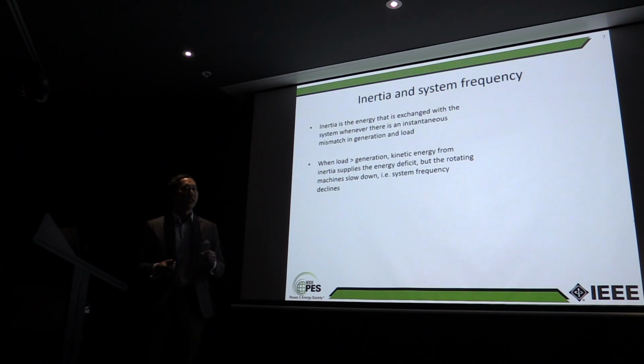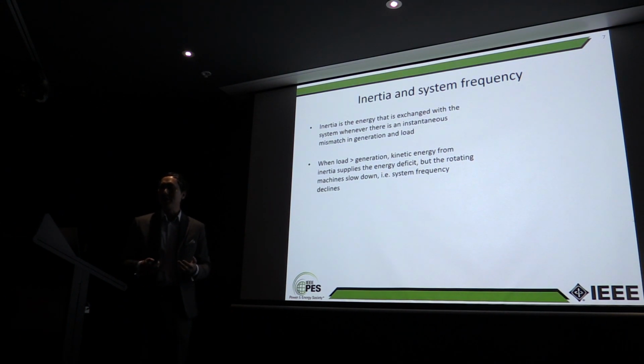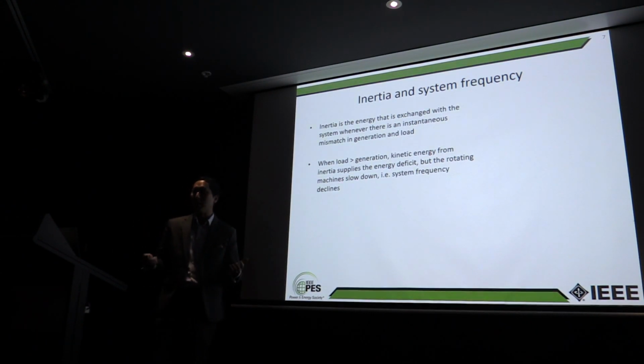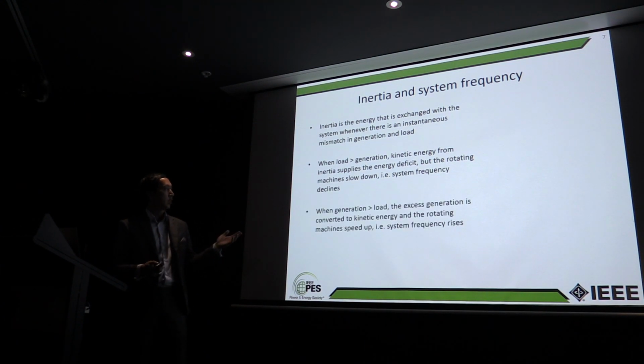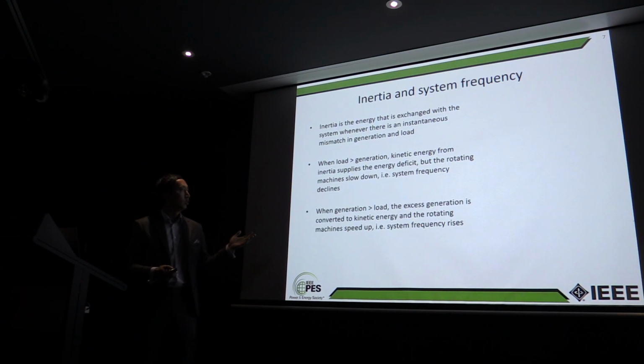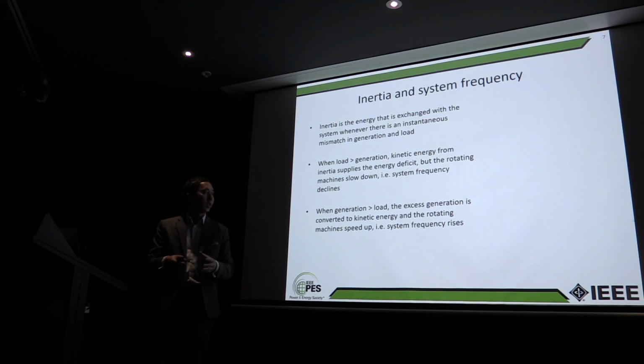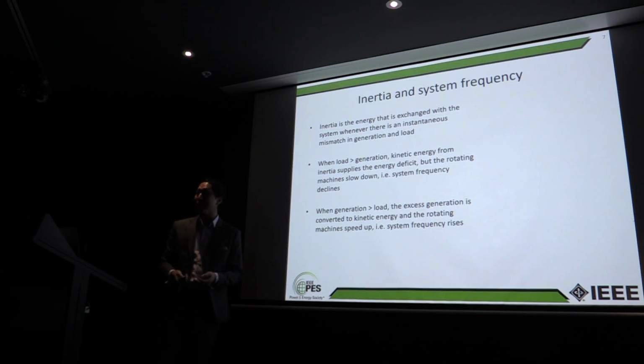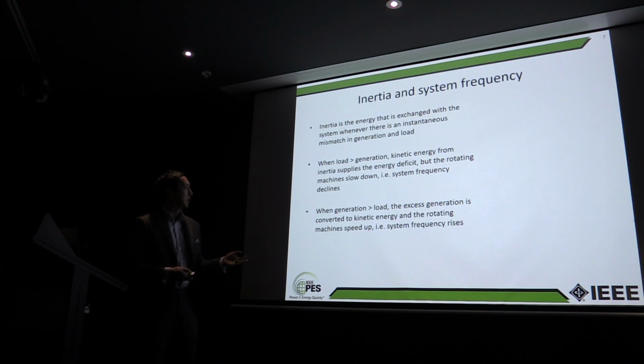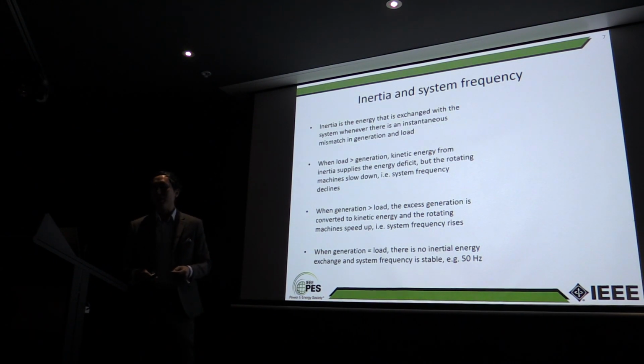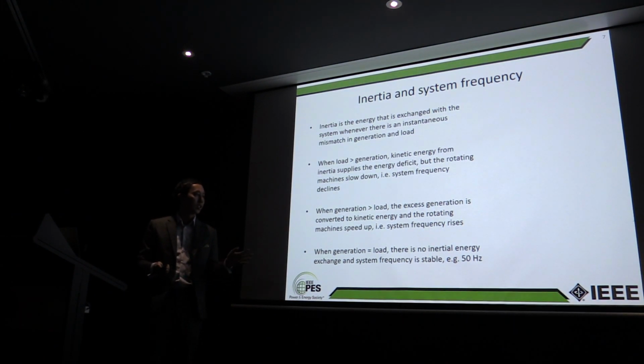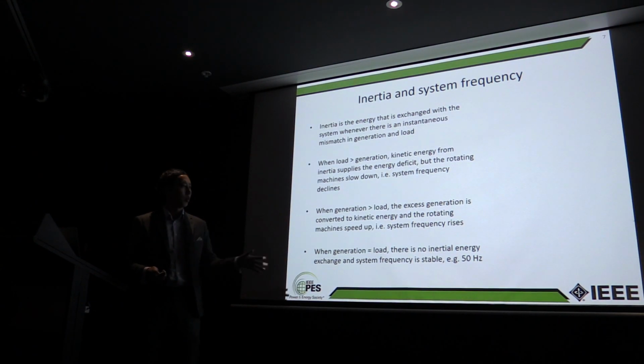If load was greater than generation, that means you have a power deficit in the system. All that kinetic energy from those rotating masses supplies that energy deficit. But in doing so, the rotation of the machine slows down, and as a result, frequency goes down, because frequency is pretty much connected with the speed of rotation. Conversely, if you have more generation than load, then you have excess energy, and that's converted into kinetic energy, the machine starts speeding up, and your frequency goes up. And obviously, the last case is when generation equals load, there's no inertial energy exchange, and your system frequency is stable. Nice 50 hertz, that's what we want.